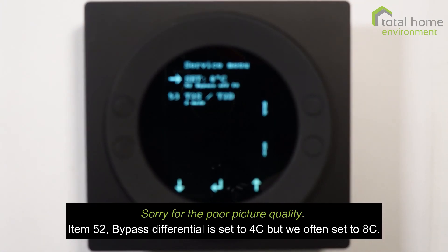Item 52, bypass differential, is set to four degrees by default but it would be much better at eight. This is a differential that determines when the bypass ceases to operate — if the fresh air temperature is more than eight degrees below your target temperature, the bypass won't work. So if the target is 21 degrees, once the outside air drops below 13 the bypass won't operate. You can stop the bypass working altogether by changing that value to zero degrees.